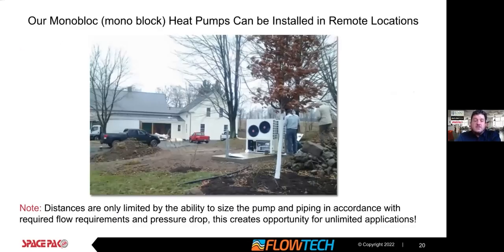Another great advantage of monoblock heat pump systems is placement of the outside unit. Our territory is California, Nevada and Hawaii, but in California, it's very difficult in some very densely populated areas to place the units. So being able to have some flexibility on that is great. These can be placed further away from the house than traditional equipment, provided the piping and the pumping are sized properly. So a big advantage is flexibility in placement.